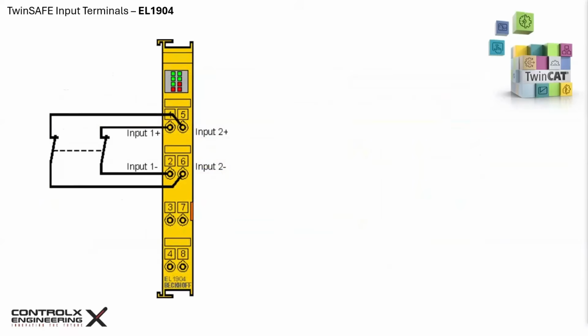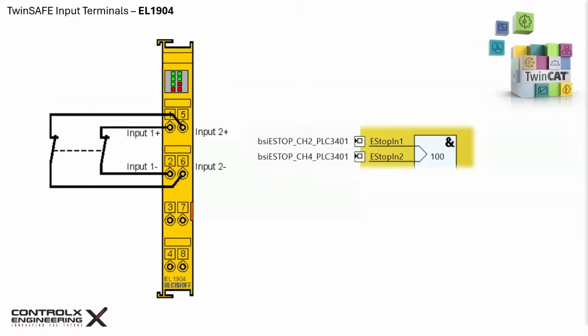To achieve the safety category 4, 2 input channels of the EL1904 must be assigned 2 different switch contacts of the same device, either 2 linked NC contacts or a linked NC and NO contact. In TwinSAFE logic, a test of discrepancy between these 2 signals must be set up. In this example, I've set up a discrepancy of 100 milliseconds between the 2 channels. If the 2 NC contacts don't open within 100 milliseconds of each other, this will cause an error.